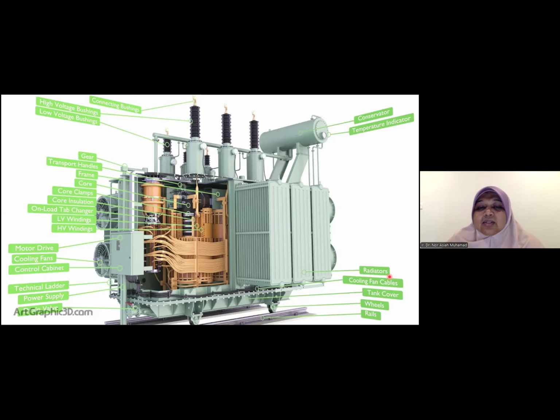We have the radiator. The oil inside the transformer has a function as an insulator and also as a cooling medium for this equipment, because this equipment operates at high current and high voltage. So there is heat dissipation inside during operation. Then we use this radiator, the same as a radiator in a car. When there is high temperature, the high temperature oil will be at the top, go down and circulate. During the circulation, the heat is released. For some transformers we add a fan to make it cool faster. It depends on the size of the transformer.